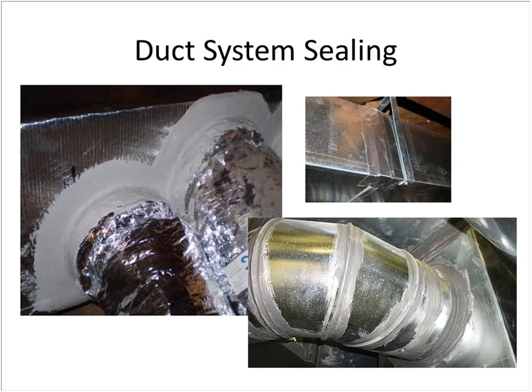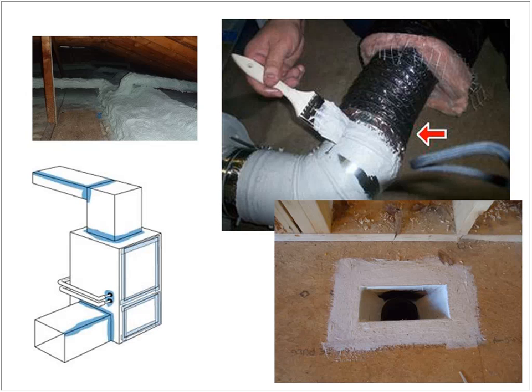Not only the transition connection between the down drop and the 6-inch duct, but also every seam on that 90-degree angle there. The top left here is ductwork that's in the attic, and it's been air sealed with a closed cell foam insulation, and that in effect is a reverse bulkhead. The problem with that is those ducts would still need to be tested because they don't have the full insulation value of the ceiling, which is an R38.